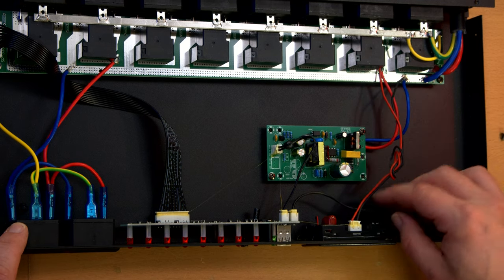Set it to AC volts and then nope, no power. Okay, so they must be normally open. Which I guess makes sense. I mean, that would be desirable. And they should all click. Oh, yeah. Nice and satisfying right there. Now, another thing I'm curious about is if they got the polarity reversed on the receptacles. I actually didn't even check that. So again, let's just see which one is live. So this one here is live on the left side, but this is upside down. Yeah, that is correct. Okay.